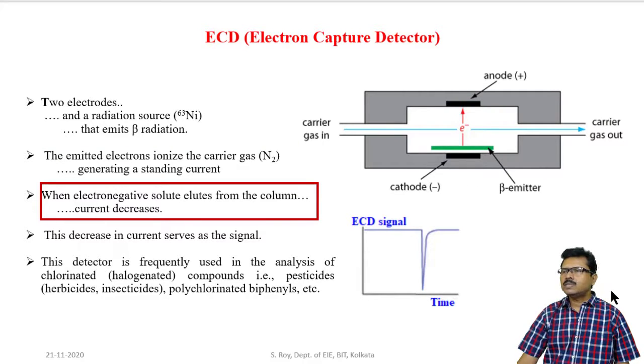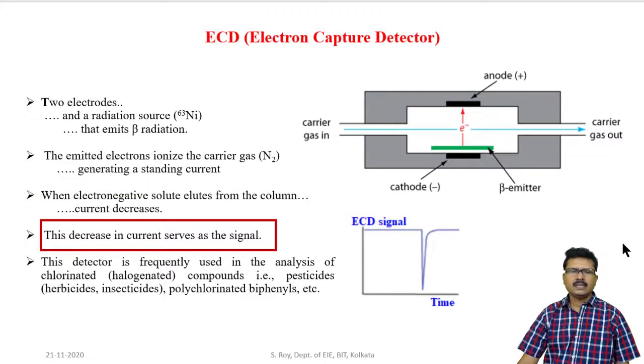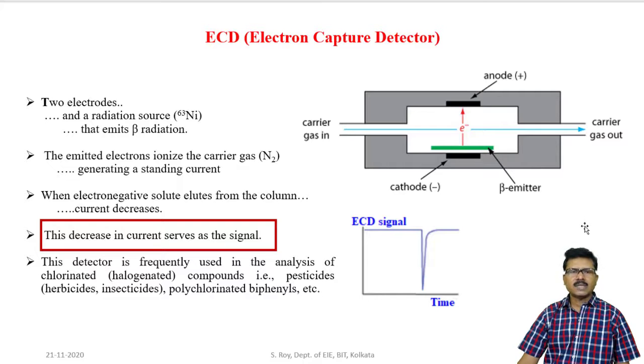When electronegative solute elutes from the column — a sample having electronegativity property — it enters into the cavity with the carrier gas. Due to its electronegativity property, it captures more electrons. So, electron flow from cathode to anode decreases, meaning fewer electrons flow inside the cavity. Therefore, current flow through the external circuit decreases. This decrease in current serves as the signal. If the concentration of the sample is higher, electron-capturing capacity is higher, so fewer electrons reach the anode and current flow will be lower. If the concentration is lower, current will be higher. The magnitude of the current gives the ultimate indication of the concentration of the sample.